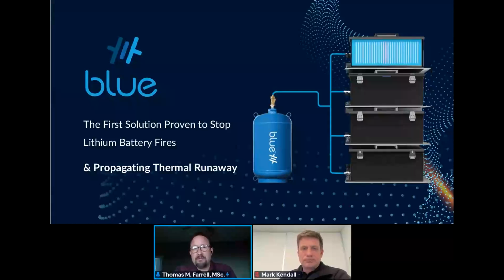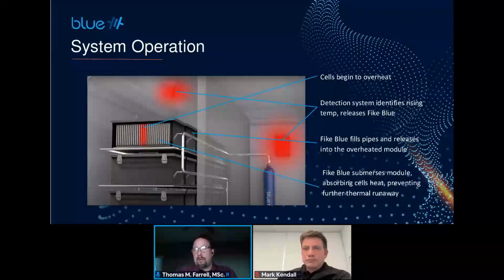This is the first solution on the market right now that, in some cases, can stop propagating thermal runaway. In other cases, it's designed to manage the thermal runaway heat as it goes through that process, if it is unable to stop the propagation based on battery design or architecture. The way it works is you have a tank of blue set near the ESS, in a manifold that is piped directly into these modules.